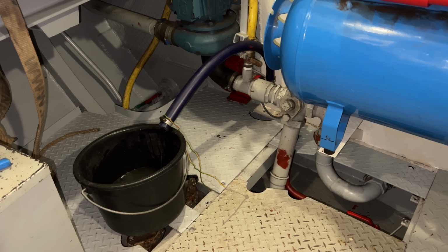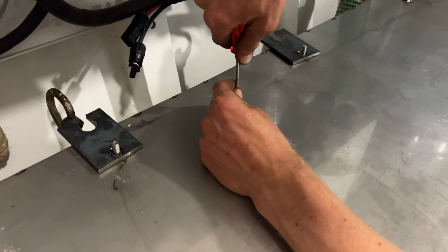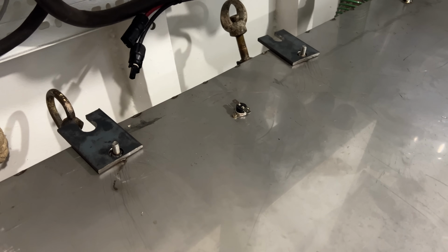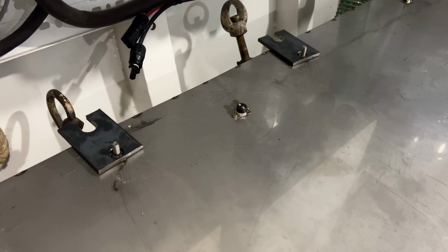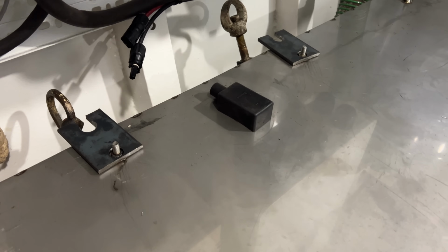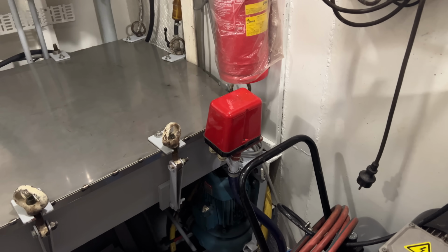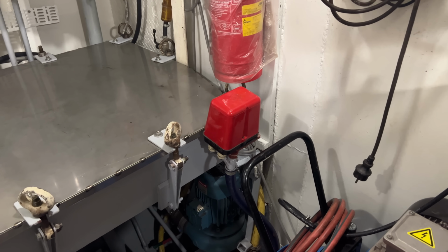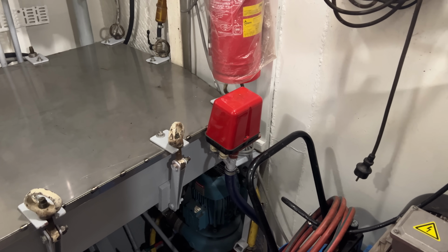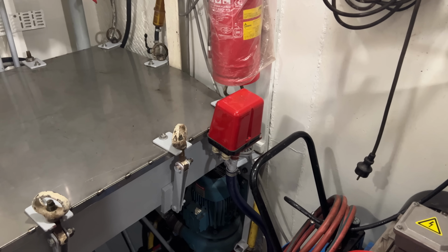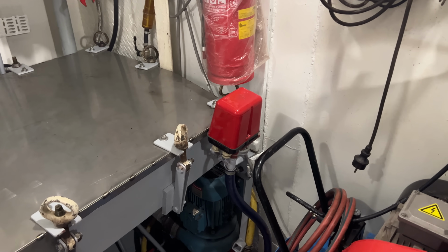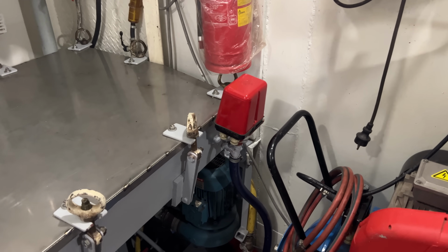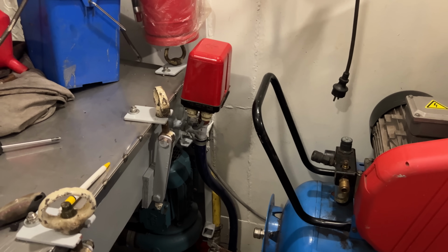Some may remember from the last video, for the total flooding system there's a temperature sensor on the lid of the battery box, which will switch on the pump at 100 degrees Celsius. And inside the box there's a sprinkler head which pops at 145 degrees. To make sure that the pump doesn't have to run for a long period against a closed sprinkler head, there's a pressure switch in the line just after the pump. It is a reused one from our old freshwater Hydro 4 unit. So it's best to check if it works as well.